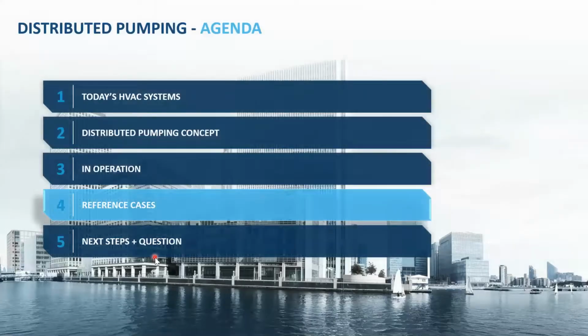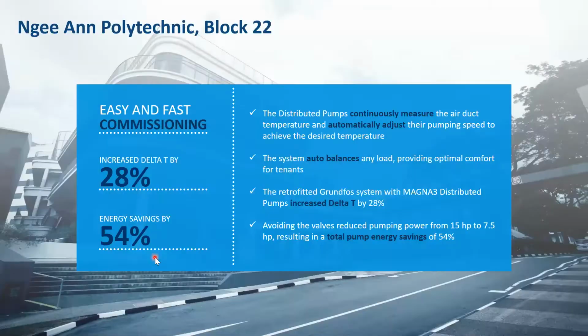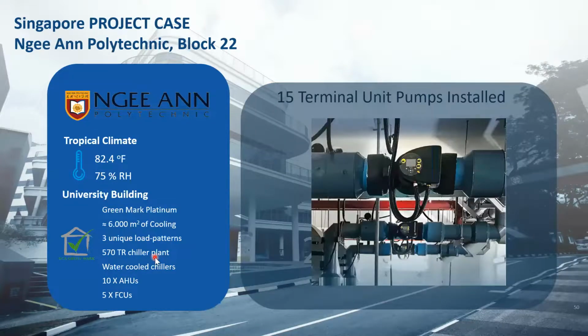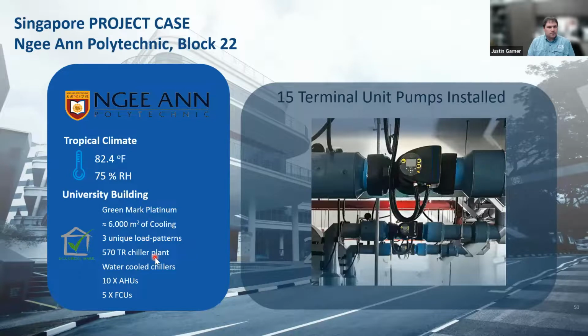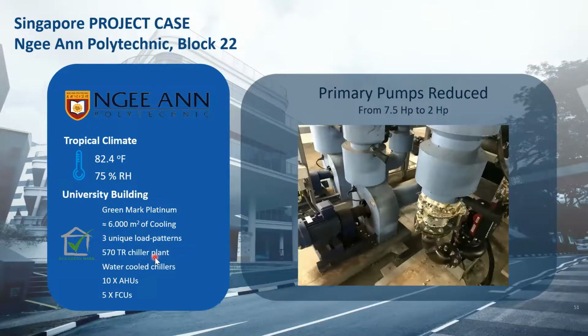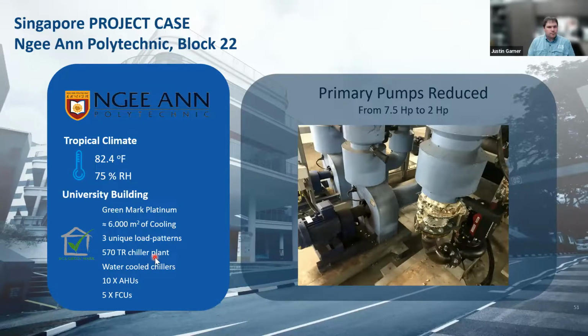All right, and the last piece before we get questions, I want to talk in a little more detail about the case study that I sort of started with and gave you very little details on. So we'll give you a little more detail on what went into achieving these savings. There were 15 terminal unit pumps installed. So we took out 15 control valves and put in 15 distributed pumps into the Block 22 building at Ngee Ann Polytechnic. The primary pumps we were able to reduce from 7.5 horsepower pumps down to 2 horsepower pumps. So a significant reduction in size and ultimately a reduction in energy to pump that primary.